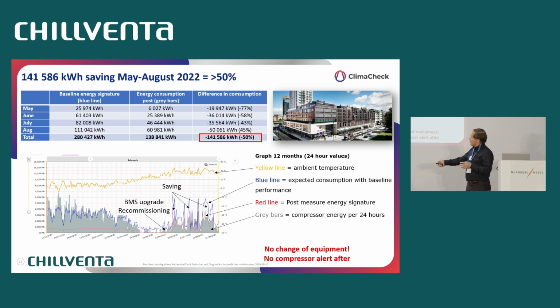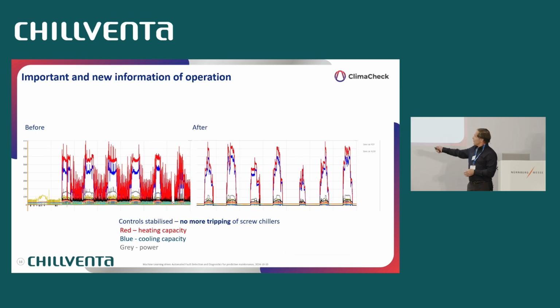And here they had a lot of tripping of the compressors on oil leaving the compressor. And when you look at this, this is a before and this is after. And this is extremely common, that the chiller has its own control and this building has its own control. You need to make sure that these work well at different load conditions. And nobody has responsibility for that. Equipment owners hear that it trips, but that's because of the consultant or because of the plumber. So there's always this debate on whose fault it is. And you just need to make sure that they work together. And it's possible.